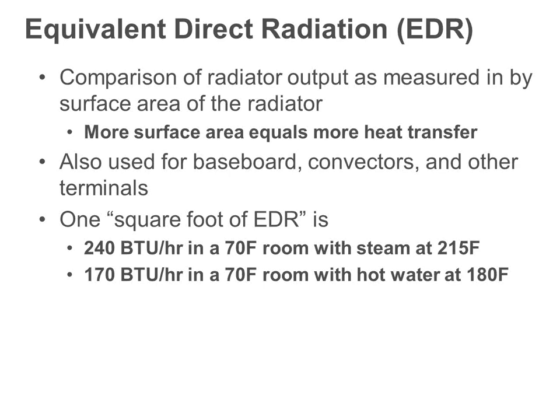When we're doing radiant floor, most people ask, well, how do I know what the tubing is, what the spacing is? The tubing and spacing are critical to the system, but really what you've got to remember, the tube is not the radiator, the floor is the radiator. All right? That actual floor is your radiator. So the ultimate highest number, and this is going way back, about the absolute most you can get out of radiant floor systems, about 50 BTUs a square foot.